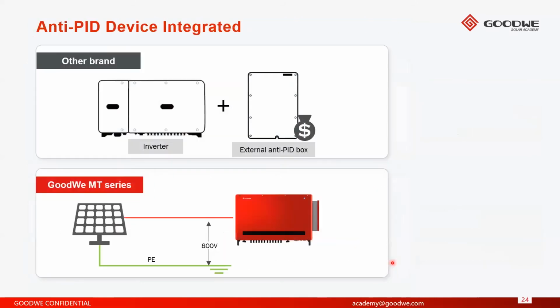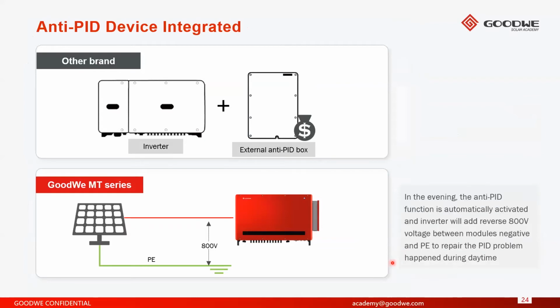Also, traditionally, inverters required external PID boxes, which also added additional costs to the PV plant. However, the GoodWe MT and the HT series has an option to have the PID box included inside the inverter itself, so reducing the need for an external box. So therefore you save costs on the box itself and the installation and the associated wiring with the anti-PID boxes.